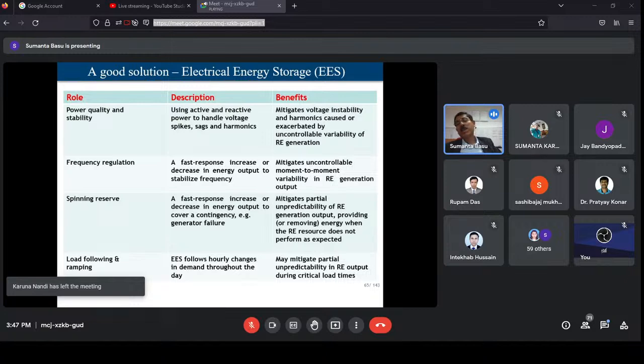Power quality and stability, because as we told, it supports your voltage stability. It reduces the harmonics caused by the exorbitant, uncontrolled variability of RE generation. Frequency regulation, of course, is moment-to-moment monitoring of the variabilities in the RE generation output. That can also be addressed. But as I told, for large-scale requirement, it is still to be worked upon and not yet proven. By 2030, the renewable energy generation will be around 62%, amounting to 500 gigawatts. So a lot of products based on recent innovations have to be in the market for the application.